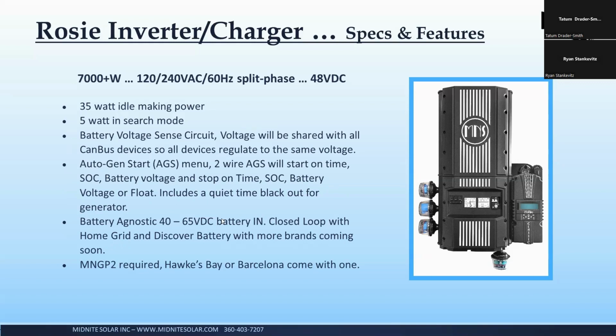Something else new for MidNite, the system has battery voltage sense. So there are a pair of terminals in every one of the products. You only need to use one, but that pair of terminals will actually allow you to connect it to the battery with small gauge wires. And that will tell the system what the actual battery voltage is. So if you've got longer cables or whatever the case may be, and there's some voltage drop under heavy load or heavy charge, that battery voltage sense will compensate for that automatically. No input needed by you. Just hook up the 2 wires.